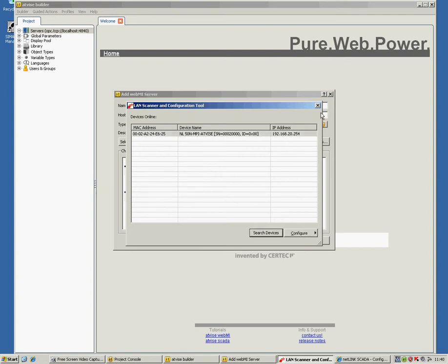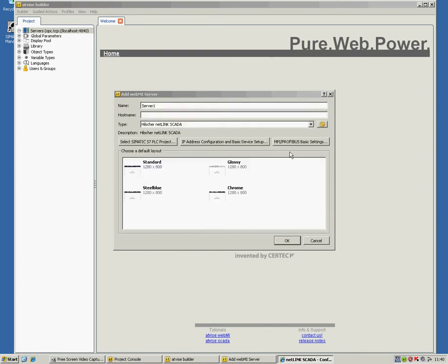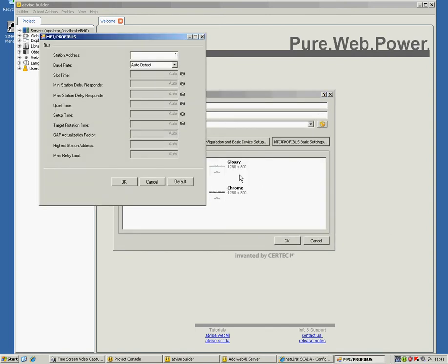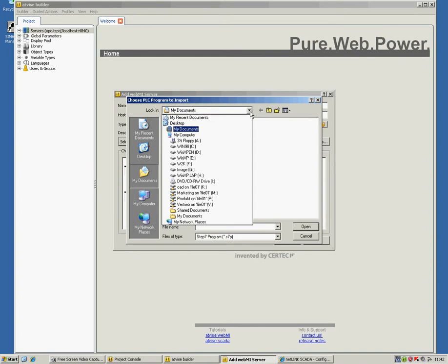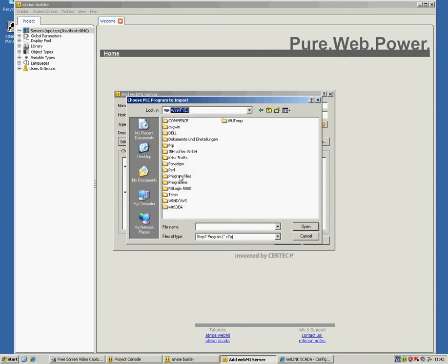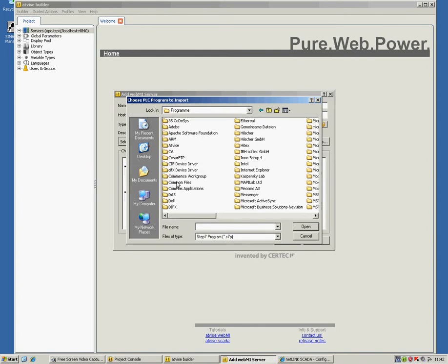Here you are. We can leave this dialog now and choose the next option, setting the bus parameters. You see a lot of parameters grayed out. This is because the default option is auto-detect. The second option you have to set up correctly is the MPI Profibus bus address. I set it to 1. The last thing that we have to do is to choose the Step 7 project that we have created before and where we want to import symbols from.